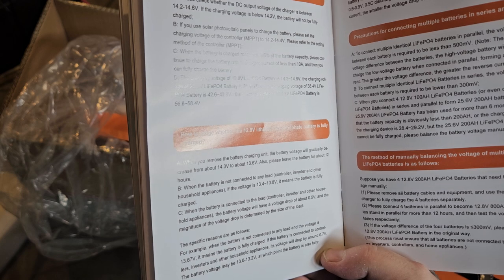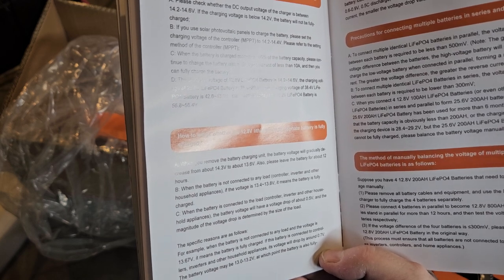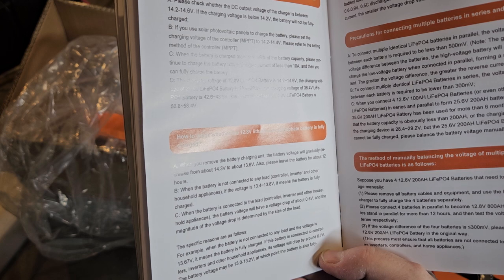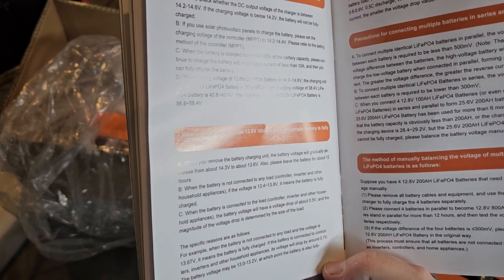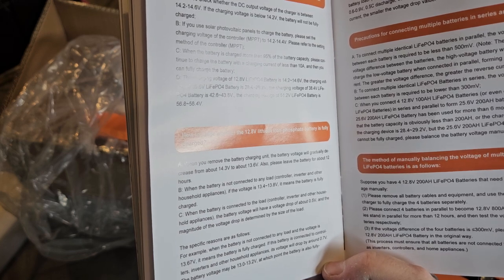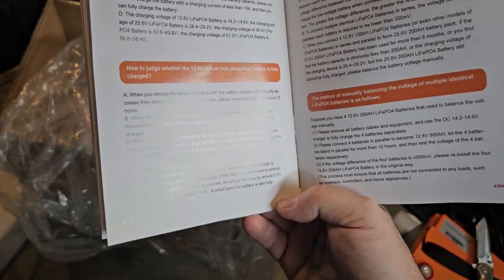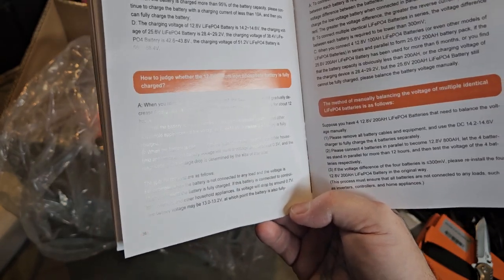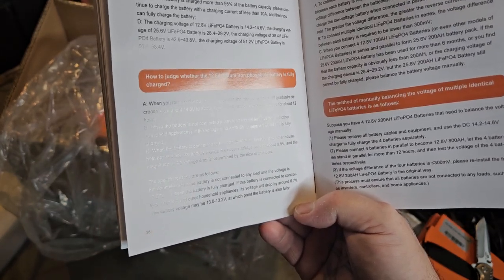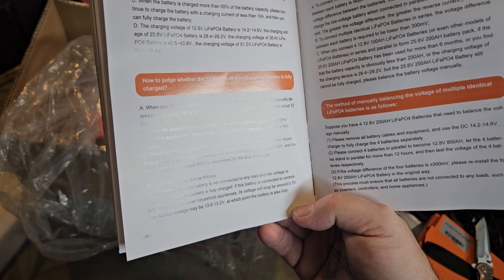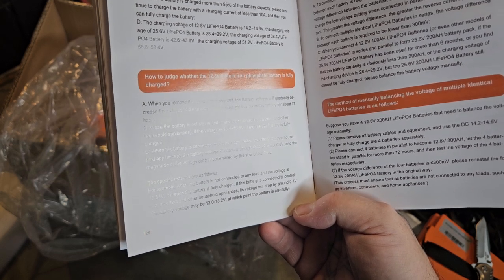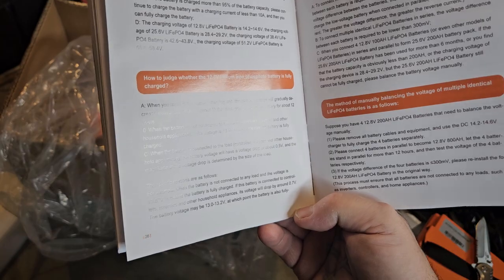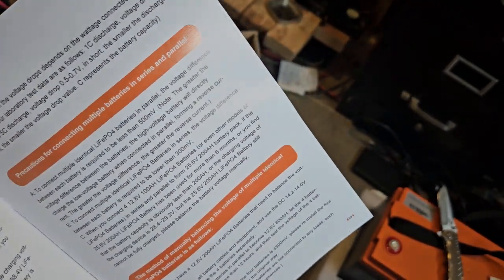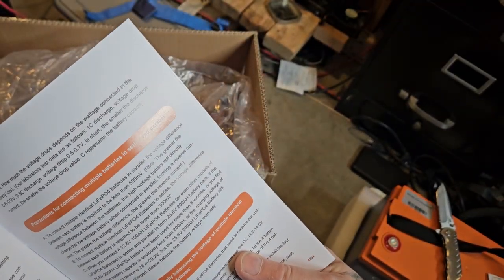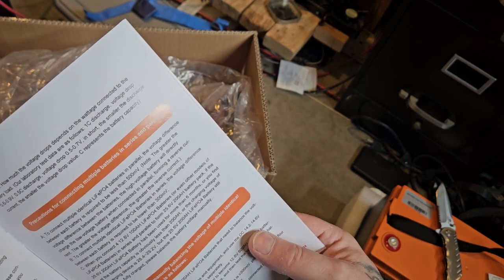When the battery is connected to the load, the voltage will drop about 0.5 volts, and the magnitude of the drop depends on the size of the load. For example, when not connected to any load, a voltage of 13.6 means fully charged. If connected to controllers, inverters, and household appliances, the voltage may drop around 0.7 volts, to 13.0 or 13.2, and the battery is still fully charged at that point. How much the voltage drops depends on the wattage connected to the battery load.